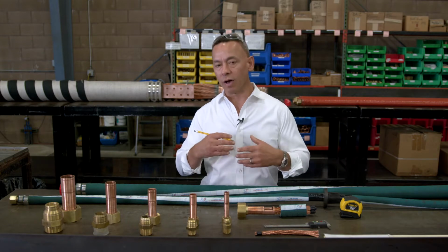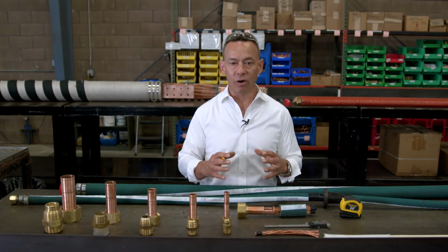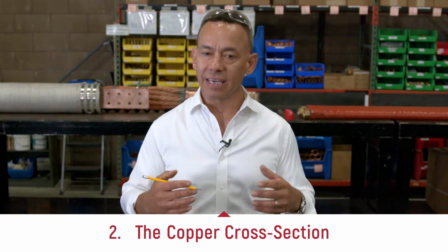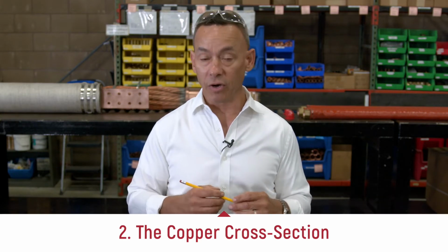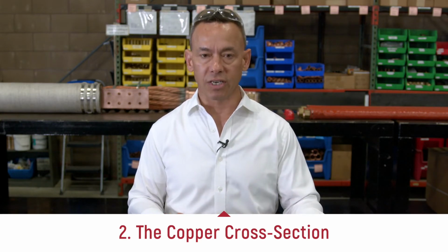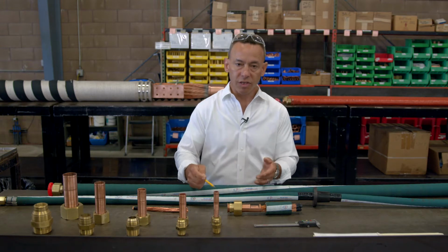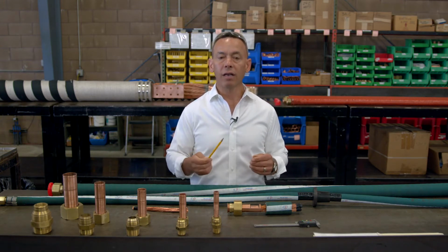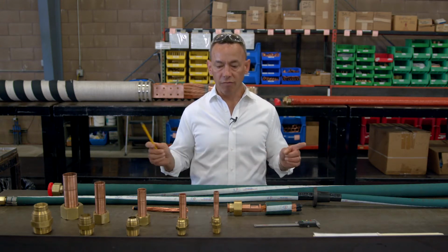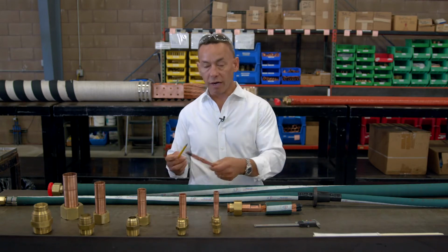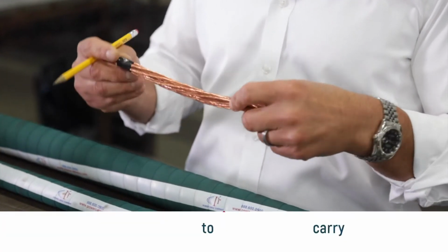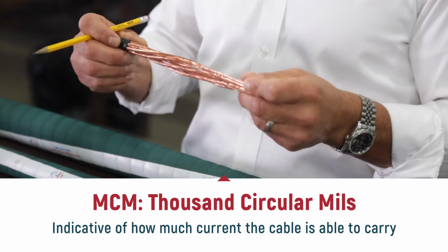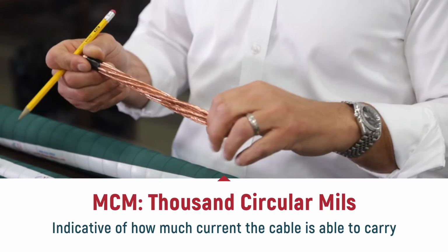So once you've determined what the ID of your hose is, it's fairly easy to calculate or figure out what your copper cross section would be. And with a 12C cable, typically you have one 2-aught conductor running the full length of the cable. This is a 2-aught conductor here. That's 133 MCM cross section, and it's indicative of how much current the cable is able to carry.